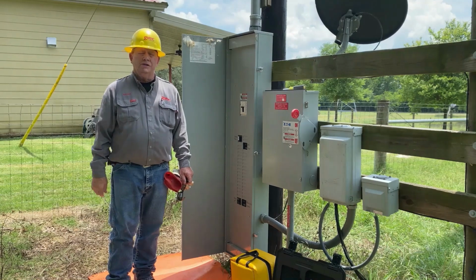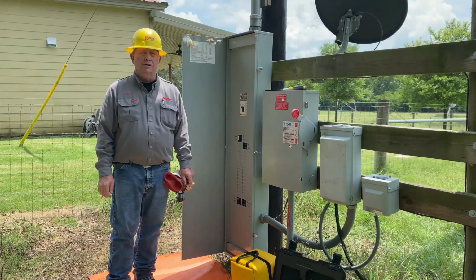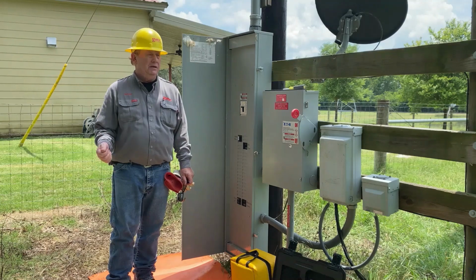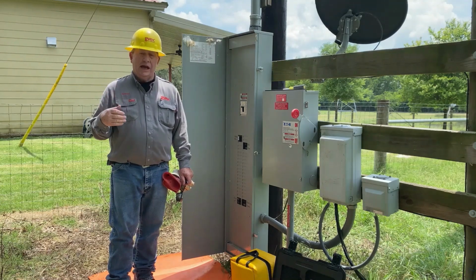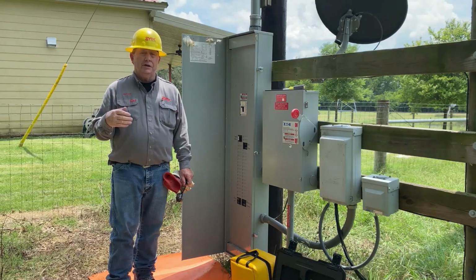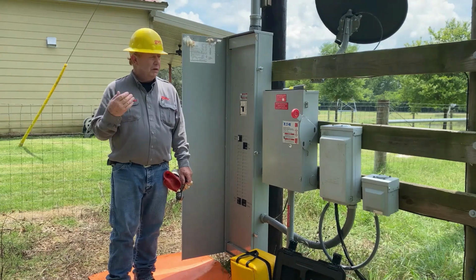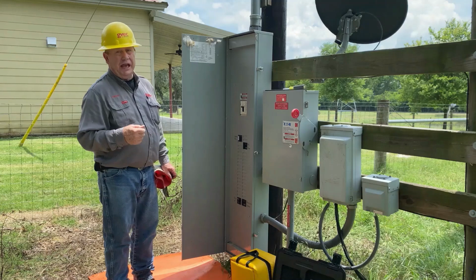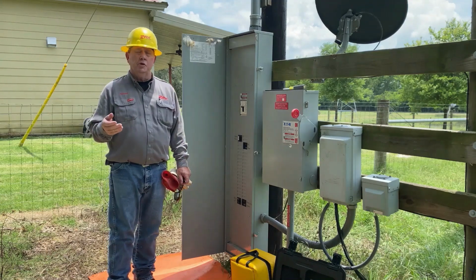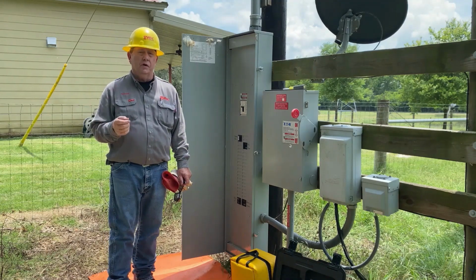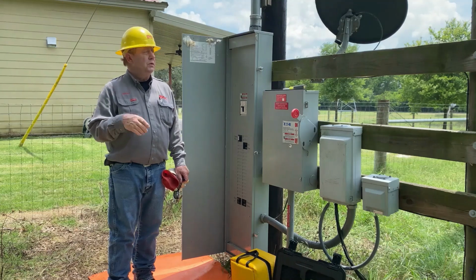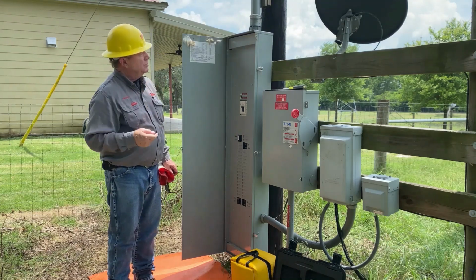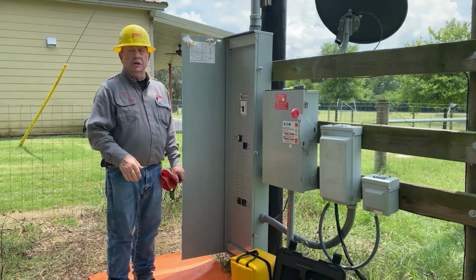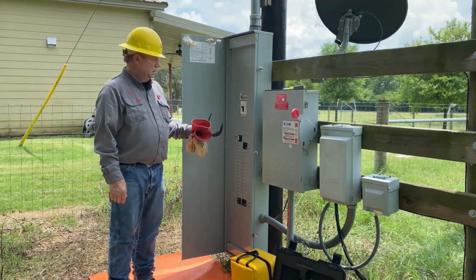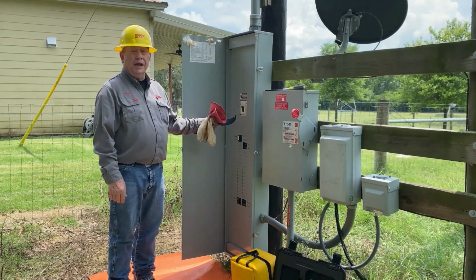Today we're going to work a service order for a voltage complaint. The complaint is the lights in the house flicker when the air conditioner starts and the dryer starts. Right now the transformer is a 50 kVA transformer that delivers 200 amps at 240 volts. We have 4-aught secondary for about 20 feet, and then it goes to the customer's riser. The main disconnect is 400 amp.